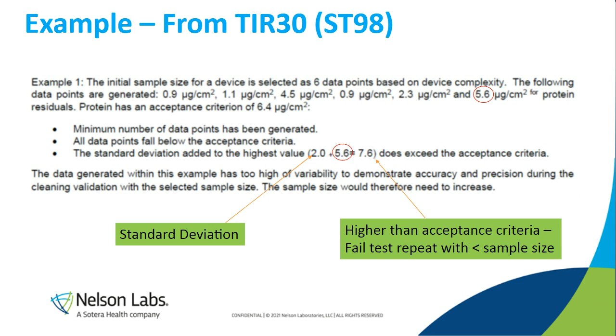Now, cleaning validation acceptance criteria. I just wanted to go over some things that have been added to the final draft for ST98 and ISO 15883-5, if you're not aware of it. We did add TOC and ATP to the ST98. The current draft of TIR30 doesn't have TOC or ATP in it, so this standard will have that.